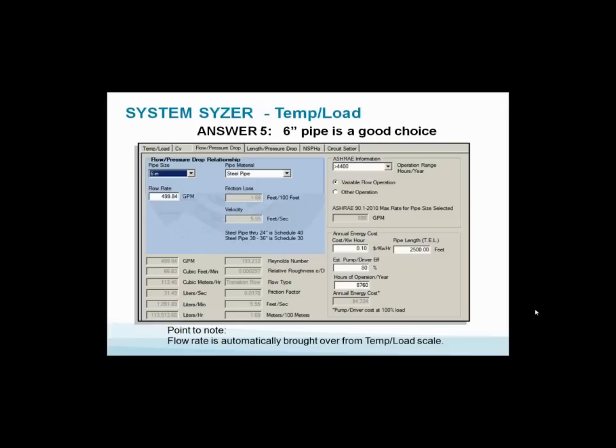You got your friction loss at 1.68 feet per 100, so we know the pressure drop per 100 feet of pipe. We have the velocity, 5.55 feet per second. You want Reynolds number? You got Reynolds number. You want feet per second? You got it. You want metric? Look at the bottom left-hand charts - you got liters per minute, liters per hour, liters per second, cubic feet, and GPM. You got feet per second, meters per 100 meters. You want to go metric, English, English to metric. What quicker way are you going to find to do this? This is just beautiful. You've got to have it.